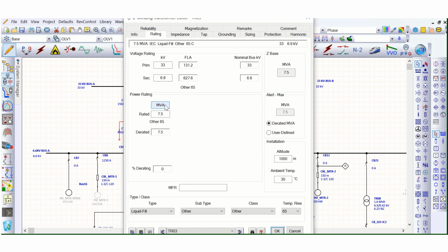This is defined as a liquid-filled transformer. So if the class is ONAN ONAF, I believe you already know this, oil natural air natural, and ONAF is oil natural air forced. So this is forced cooling, the transformer rating will be improved during the overload condition. The transformer will move from ONAN to ONAF rating.